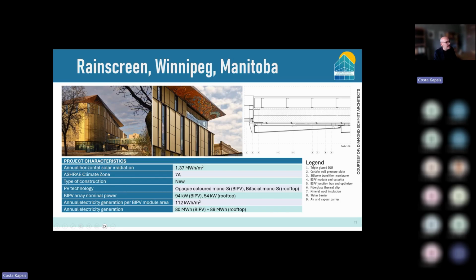The cavity is ventilated, with a junction box and cables that run through railings through our facades. Same modules with the same orientation and size are wired together in series, and these strings are wired in parallel with another string. That final DC cable comes inside the electrical room, connected to electrical equipment and an inverter to transform solar electricity collected from your facade into AC usable electricity for your building.